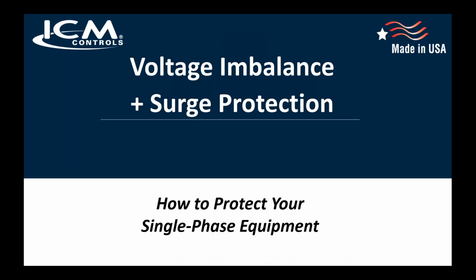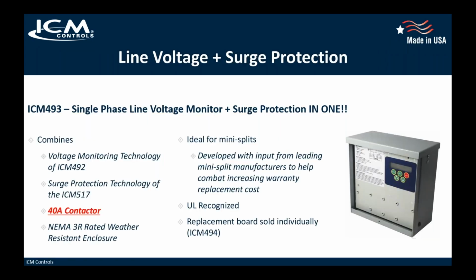All right, so how do we combine both voltage unbalance and surge protection in one device? Well, the answer to that was the 493. What we did is we took the two pieces of equipment we just mentioned, the voltage monitor and the surge suppressor, and the benefits of both, and combined them into one unit for 220-volt, 240-volt applications. Where this really took off was in the mini-split market. So the 493 is the answer to marrying those two types of devices together. The ICM 493 has both the voltage monitoring capabilities of the 492 plus the surge protection technology of the 517.